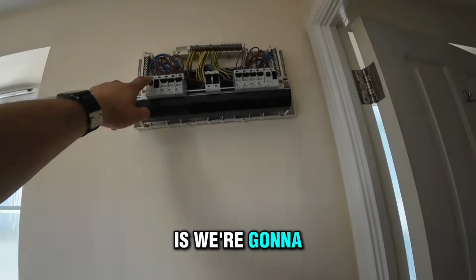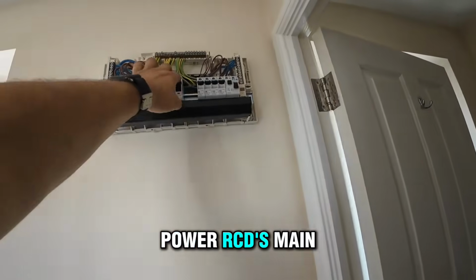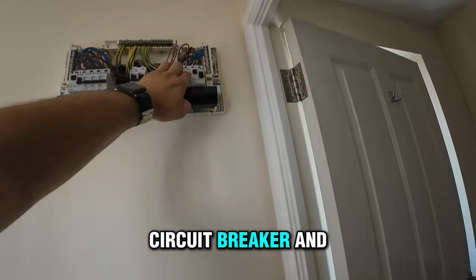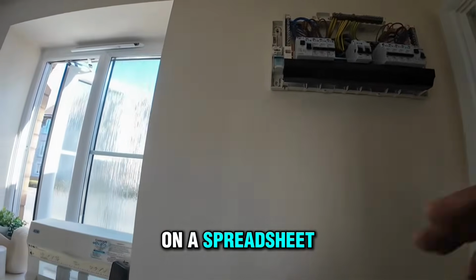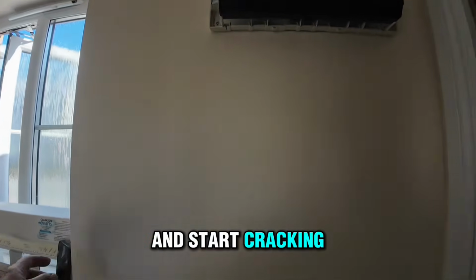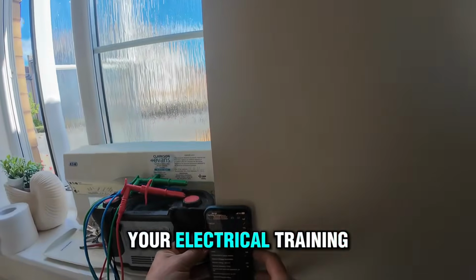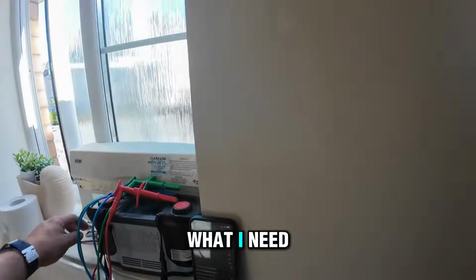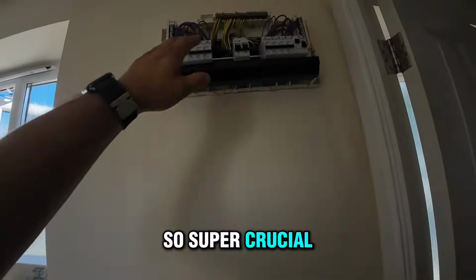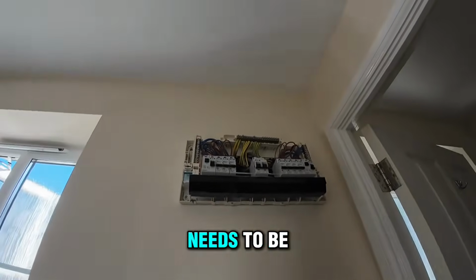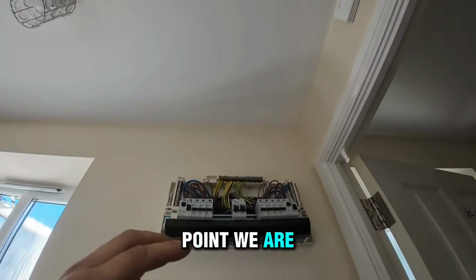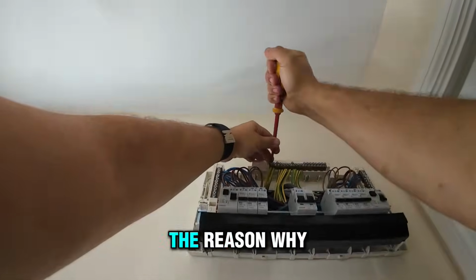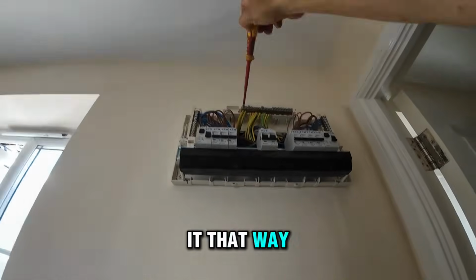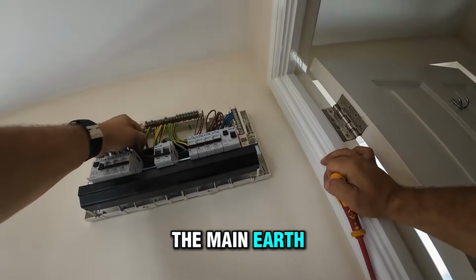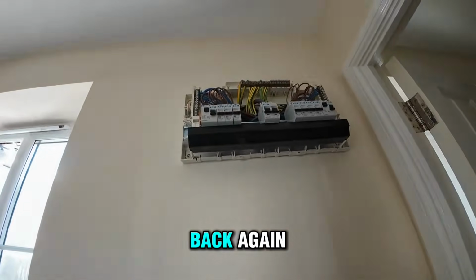For now, we're going to actually kill the power: RCDs, main switch, each circuit breaker, and put the information on a spreadsheet and start cracking on with the testing. If you've done your electrical training, you will know what I need to do now. Super crucial, the whole installation needs to be off, and at this point we are removing the main earth. The reason why this is so important to do in sequence is that after removing the main earth, we need to make sure that we put it back again before we do anything else.